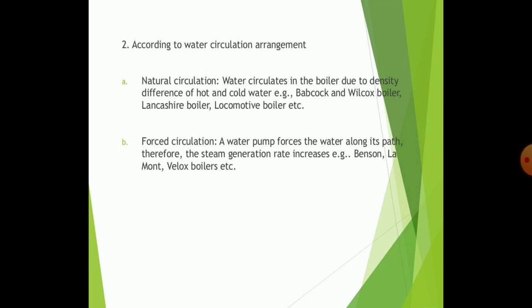We can achieve steam generation with many other methods as well. If there is an arrangement of water circulation, boilers can be classified according to the circulation of water — that is, natural circulation and forced circulation. If water circulates due to the density difference of hot and cold water, for example in Babcock and Wilcox boiler, it is called natural circulation. If a water pump or external force is required to move the water along the path, such boilers are said to have forced circulation, as seen in Benson and Lamont boilers.